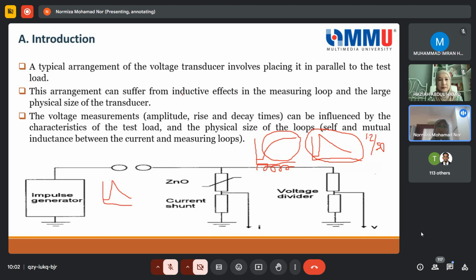So because of this inductive effect, it gives different results. It means that your measuring device will not give you a fast response as 1.2/50. So that's why it is important to first calibrate the measuring device before we proceed to the real test. But that one we will cover in general, how to do this calibration test. I know that testing is normally included in the high voltage engineering subject.